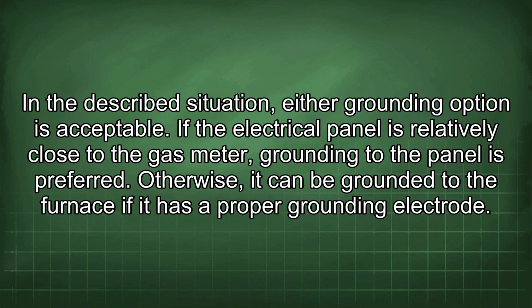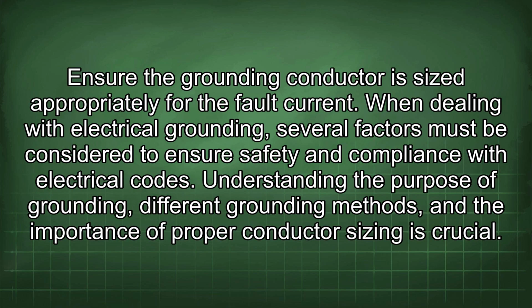In the described situation, either grounding option is acceptable. If the electrical panel is relatively close to the gas meter, grounding to the panel is preferred. Otherwise, it can be grounded to the furnace if it has a proper grounding electrode. Ensure the grounding conductor is sized appropriately for the fault current.